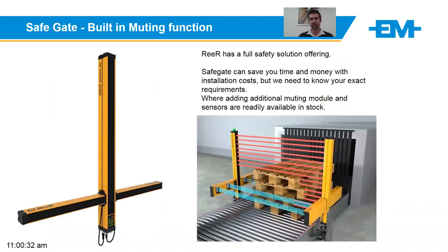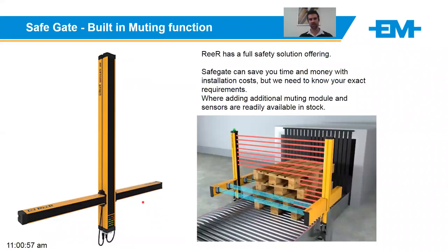ReeR has a full safety offering, too large for us to stock every single item. So with regards to the muting, they have a specific module as well. They call it SafeGate. This comes with built-in muting arms that you can adjust up and down depending on where you want the muting action to happen. And all the photoelectric sensors are integrated into the receiver and the emitter. This obviously saves time in installation, as you don't have to align a lot of different sensors, and also the wiring is a lot quicker.